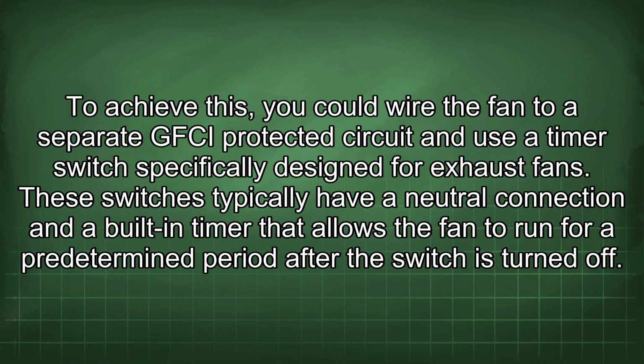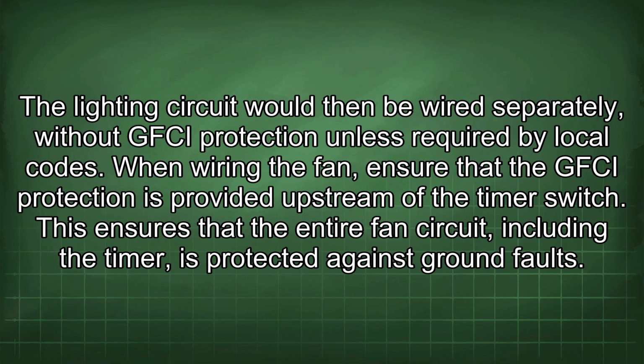To achieve this, you could wire the fan to a separate GFCI protected circuit and use a timer switch specifically designed for exhaust fans. These switches typically have a neutral connection and a built-in timer that allows the fan to run for a predetermined period after the switch is turned off. The lighting circuit would then be wired separately without GFCI protection unless required by local codes.